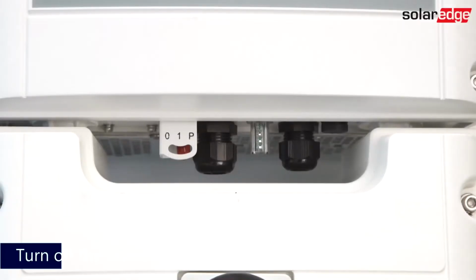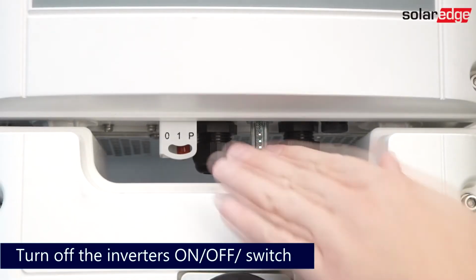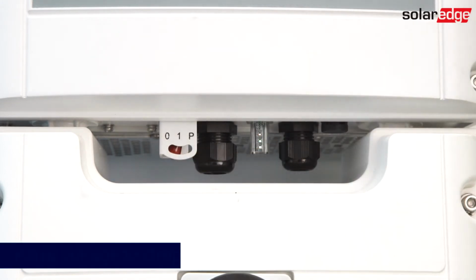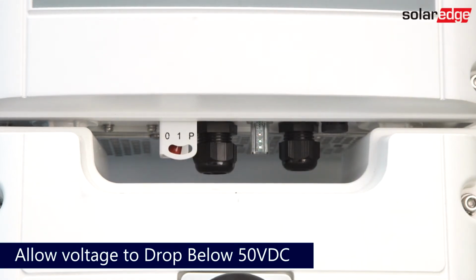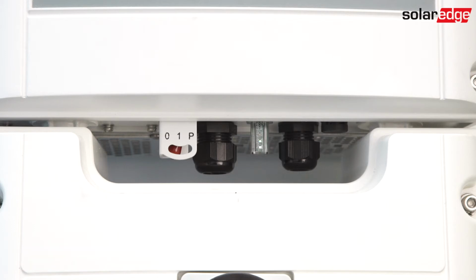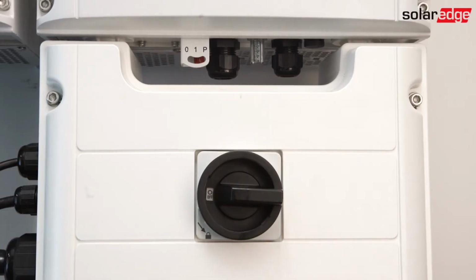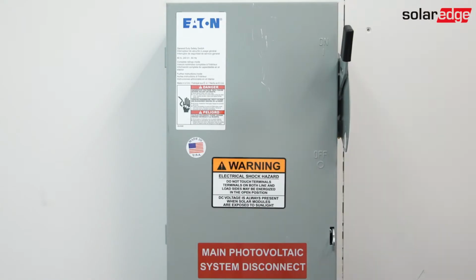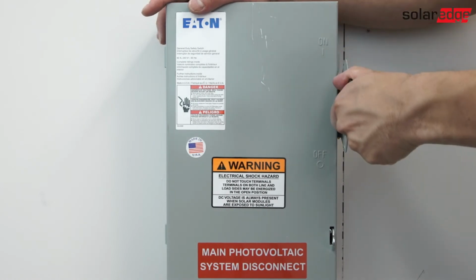Before we begin, ensure the system is completely de-energized. Turn the inverter on-off P-switch to the off position. Allow the inverter to reach safe DC voltage, indicated by the red LED light going away on the LED tube, or the voltage falling below 50 volts DC. Next, turn off the DC safety switch, and finally, ensure AC power is off.